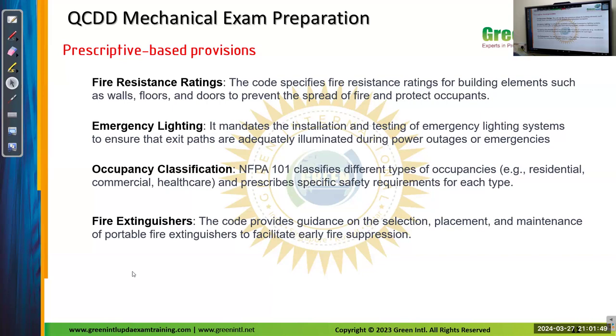You don't have to do any design calculation on whether we need 1.5 hour or 2 hour or not. You don't have to do anything. You just have to follow the standard means of egress. This is the occupancy level. This is the hazard level. Then you have to follow this 1.5 hour or 2 hour. That is a set of standards.